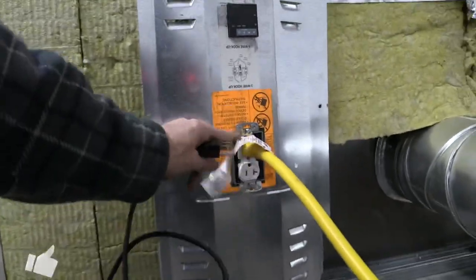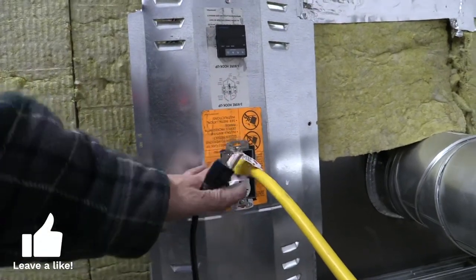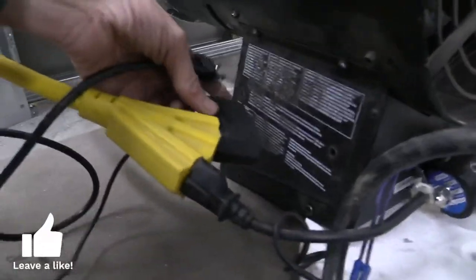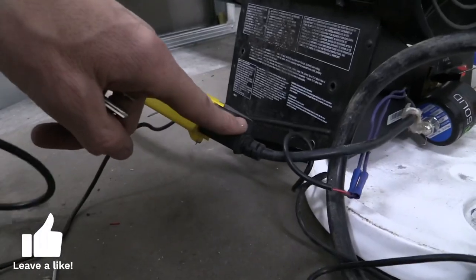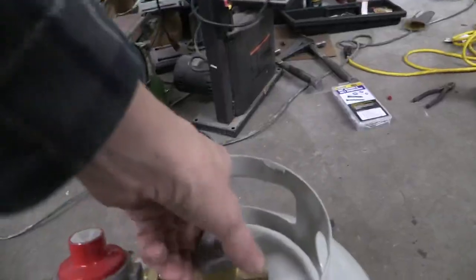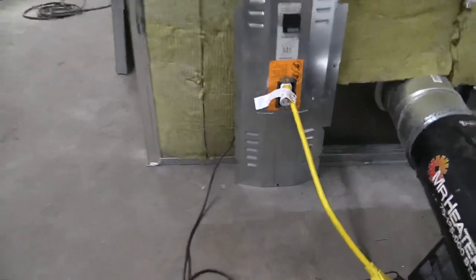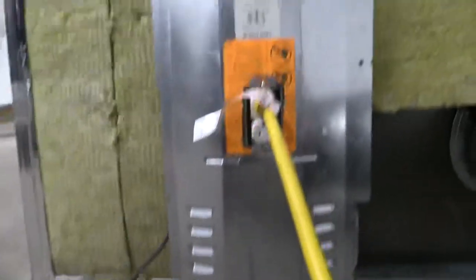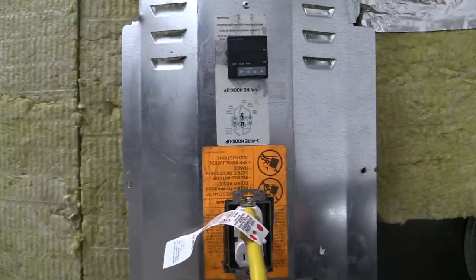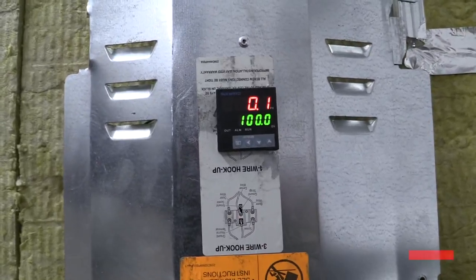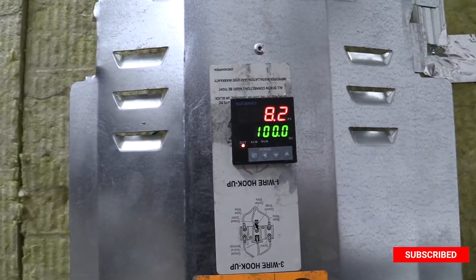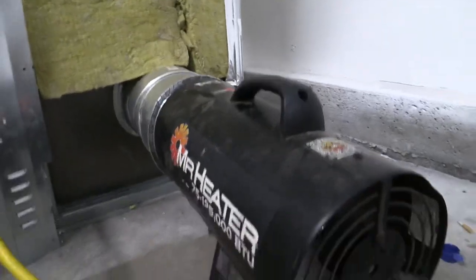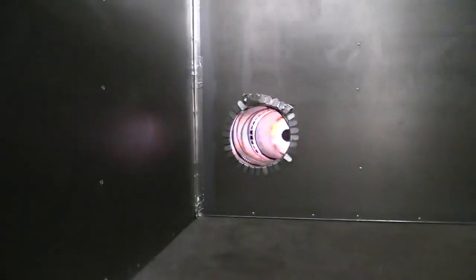This is the plug to our solenoid, this is the plug to the blower. All I have to do is turn the propane on. Now I'm going to plug this in right here, but what I'm going to do is I want you to see this because it happens quick. So I plug it in, it registers, it says yo, you need to be 100. It's definitely not 100, it's only 8. So it kicks the blower on, it opens this solenoid to let the gas through, and we've got heat.